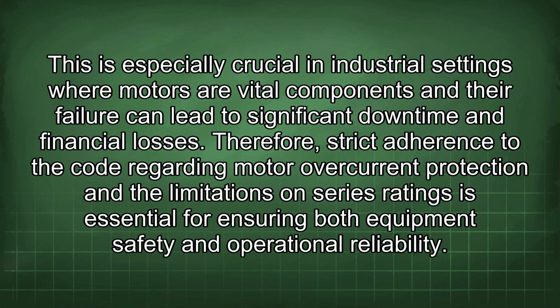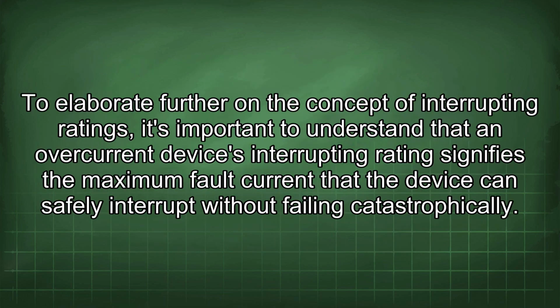This is especially crucial in industrial settings where motors are vital components and their failure can lead to significant downtime and financial losses. Therefore, strict adherence to the code regarding motor overcurrent protection and the limitations on series ratings is essential for ensuring both equipment safety and operational reliability. To elaborate further on the concept of interrupting ratings, it's important to understand that an overcurrent device's interrupting rating signifies the maximum fault current that the device can safely interrupt without failing catastrophically.